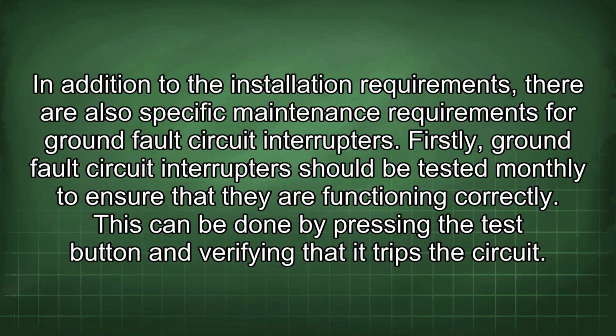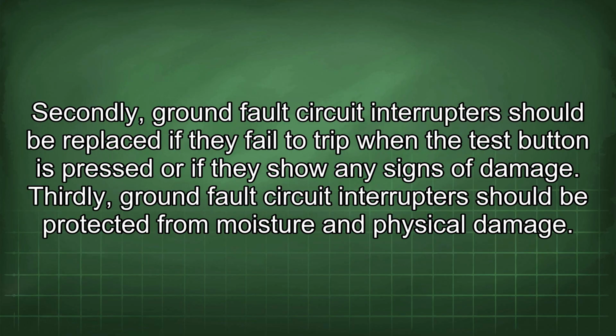In addition to the installation requirements, there are also specific maintenance requirements for ground fault circuit interrupters. Firstly, they should be tested monthly to ensure that they are functioning correctly. This can be done by pressing the test button and verifying that it trips the circuit. Secondly, they should be replaced if they fail to trip when the test button is pressed or if they show any signs of damage. Thirdly, they should be protected from moisture and physical damage.